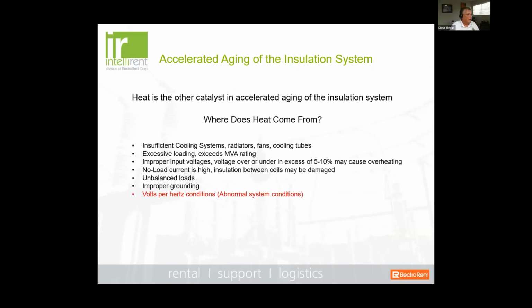Okay, so the next thing we have to be concerned about with the insulation system is heat. Okay, excessive heat. And where does excessive heat come from? Well, it can come from inefficient cooling systems, radiators, fans, cooling tubes, excessive loading. Okay, that's a big one, especially in distribution applications. Improper input voltages, or voltage over or under in excess of 5 to 10% can cause overheating. No load current is high and you have insulation between coils that may be damaged, unbalanced loads, improper grounding.